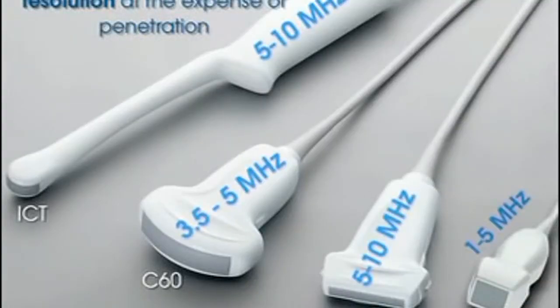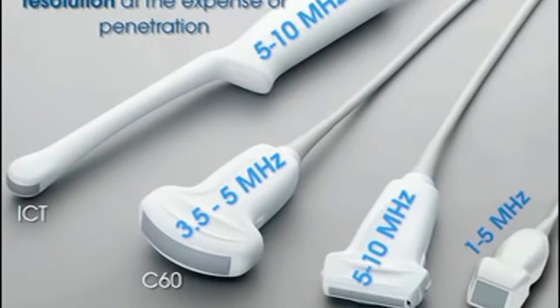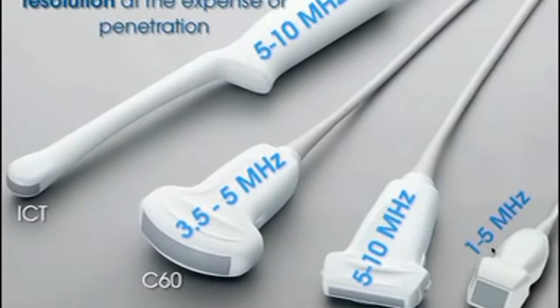Transducers have different frequencies they can toggle. Higher frequency transducers have better resolution but cannot penetrate as far into the body. A high-frequency linear transducer is good for superficial structures when depth of penetration is not a concern. A lower frequency transducer is good for penetrating deeper into body tissues, such as when doing a FAST exam or looking at the heart or aorta — at the expense of resolution. You always want to use the highest possible frequency that will get you to the depth of interest.